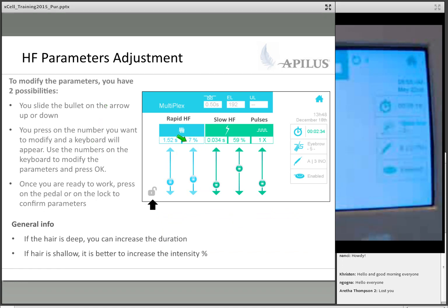So, adjusting the parameters, we've talked a little bit about how you can navigate the screen here. We have the presets, and as you've seen, we can actually change any of these numbers. So this needs to be unlocked, and then you can move the scroll bars, type in the numbers, tap on the arrowheads in order to increase or decrease any of the settings that are here. So the machine is completely customizable, even though there are the presets. The presets are really well adjusted for thermolysis. And so usually I would say just stick to the presets with the boosters that are available now and all of the different fine tunings that you can do with the probes. There should really not be too much of a reason for you to start messing with these numbers here. Once you get to know the machine really well, of course, a lot of electrologists that are really comfortable with the machine can definitely start to play around with the settings and do a bunch of different things.